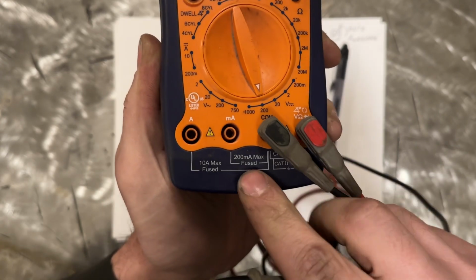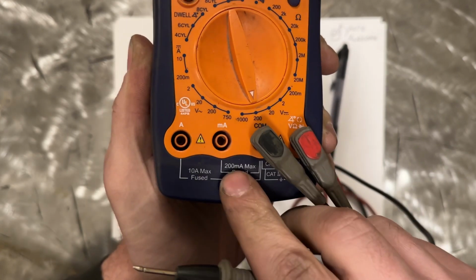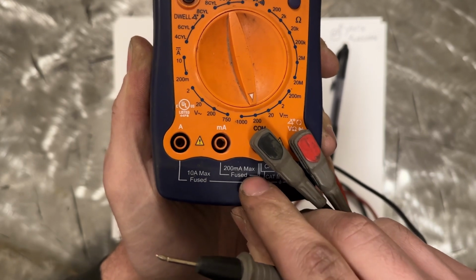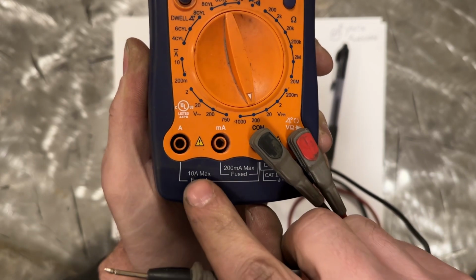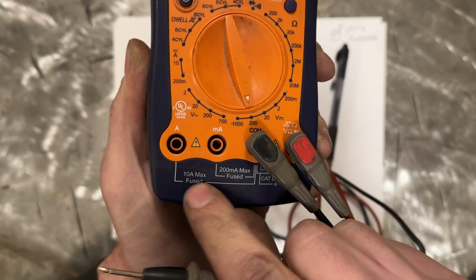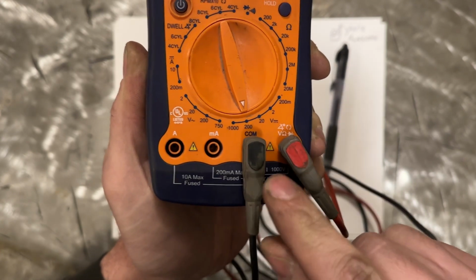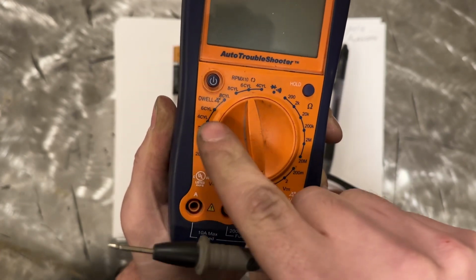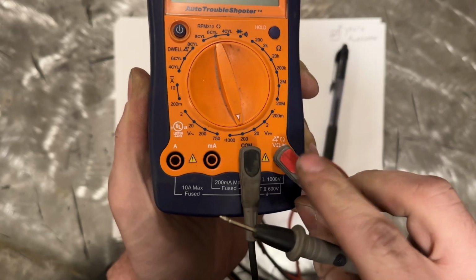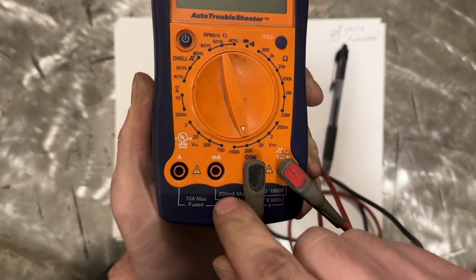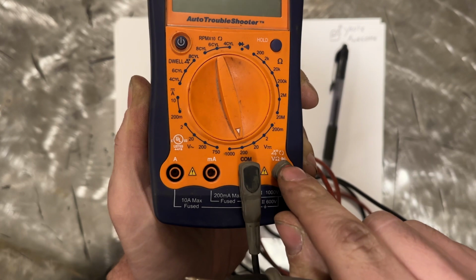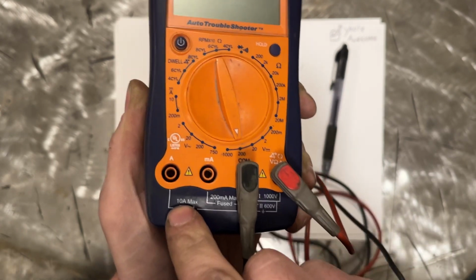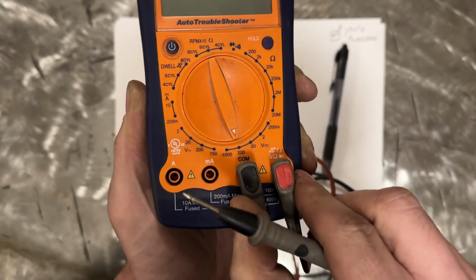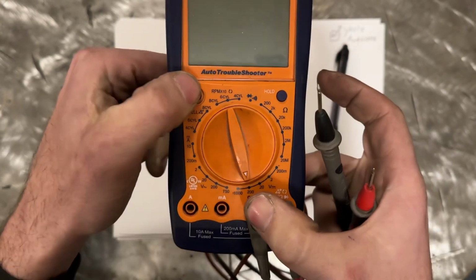When you come over here, you see how these hookups say 200 milliamps max fused. And then this one says 10 amps fused. So in order to do load checks to see how much current something is drawing, you have to move this to here for anything up to 200 milliamps, this over here for up to 10 amps. But we're testing voltage, so we're good right there.